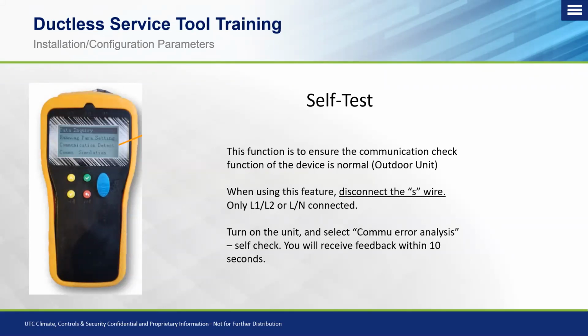We're disconnecting the signal wire that actually comes from the indoor unit, and we're wiring in our signal wire from our tool to the signal terminal on the bus bar. Okay, once we have that wired in, we're going to go ahead and turn on the unit. We're going to go to our communication simulation menu, enter into there, select self-test.